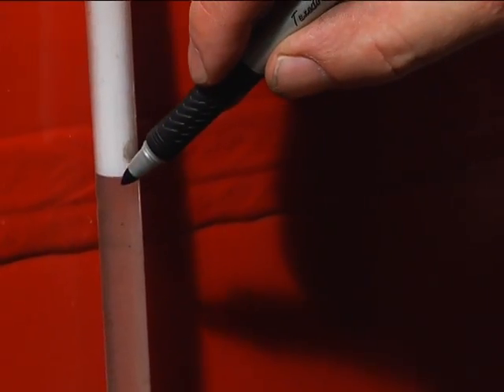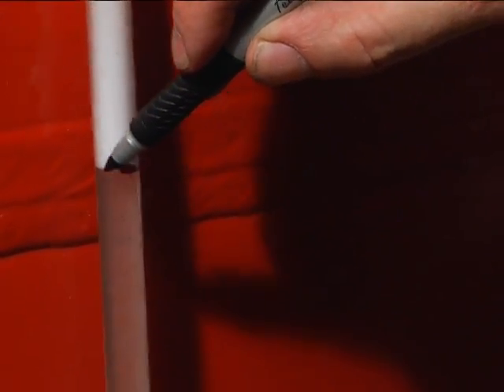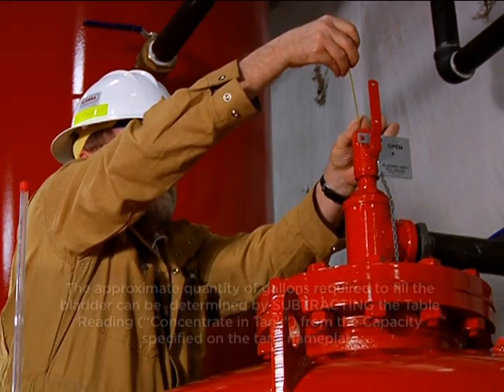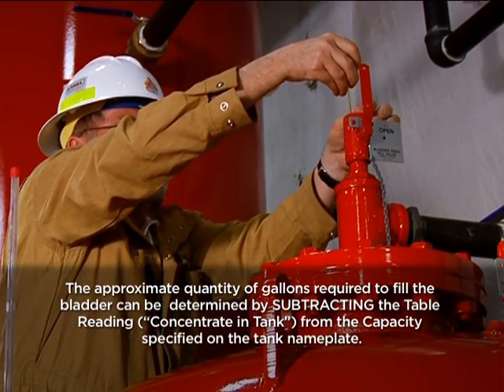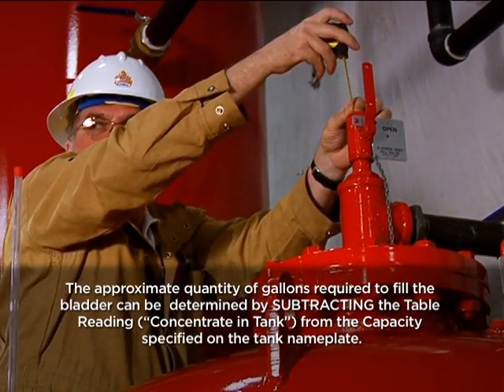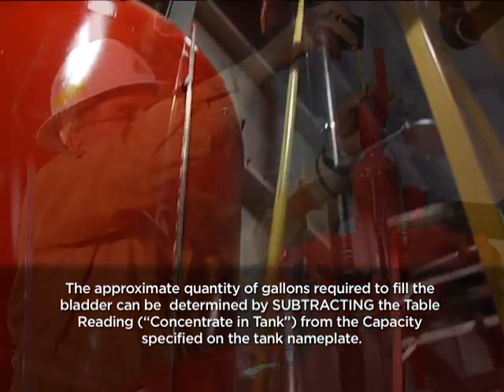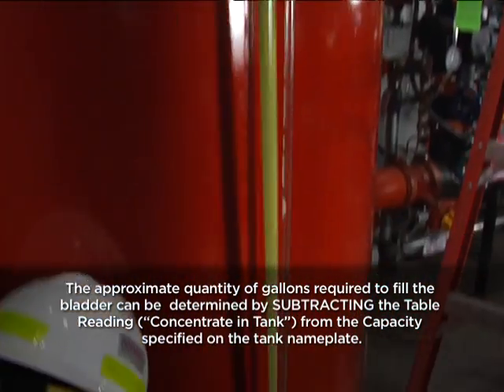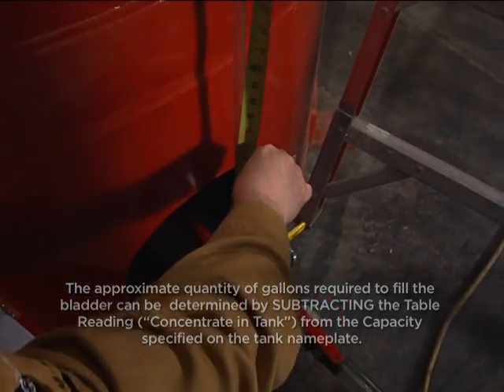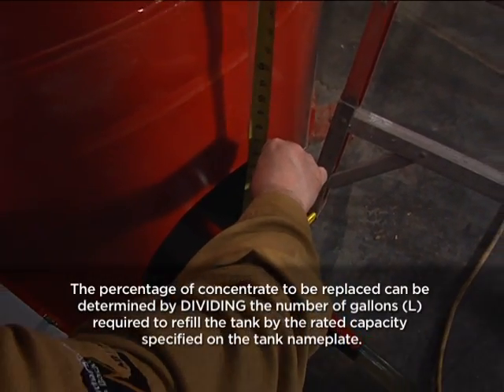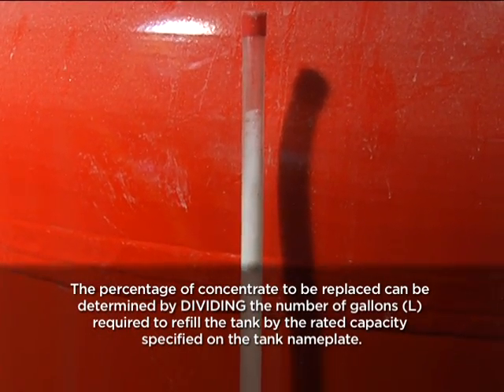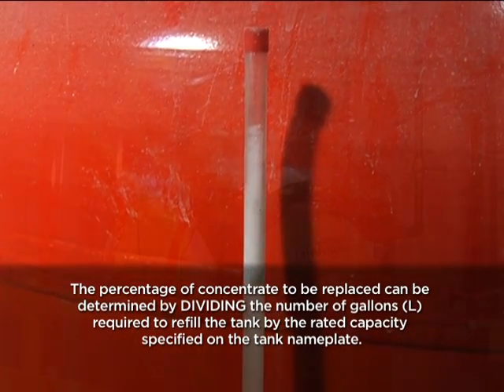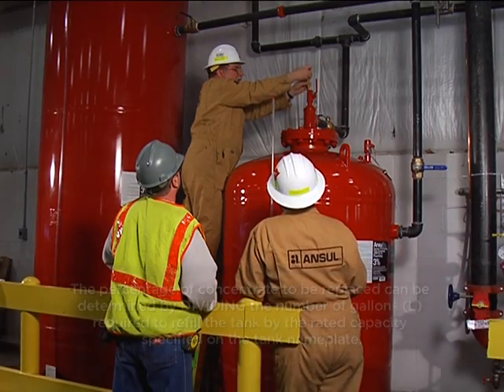The following measurements will provide an estimate of the amount of concentrate remaining in the tank after operation. The approximate quantity of gallons or liters required to refill the bladder can be determined by subtracting the table reading, concentrate in the tank, from the capacity specified on the tank nameplate. The percentage of concentrate to be replaced can be determined by dividing the number of gallons or liters required to refill the tank by the rated capacity specified on the tank nameplate.